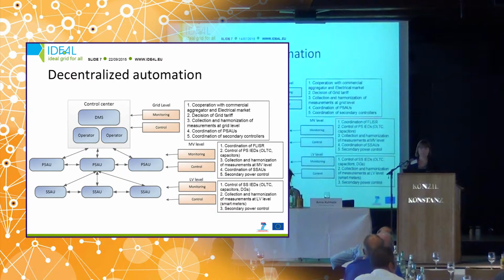This architecture consists of adding substation automation units both to primary substations and to secondary substations. The primary substation automation units will be responsible for monitoring and controlling the medium voltage network, and the secondary substation automation units will be responsible for monitoring and controlling the low voltage networks. Only the necessary data is transferred between these different substation automation units and the control center, so not all the data needs to be transferred throughout the whole network.